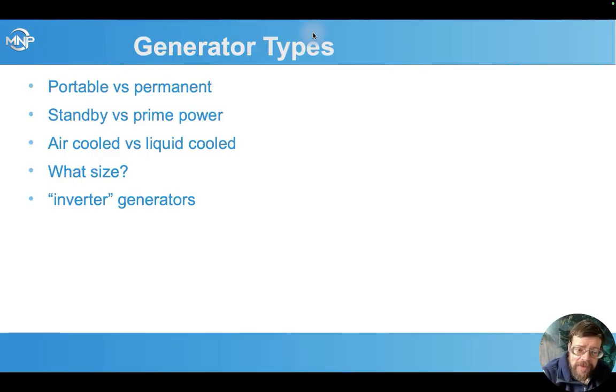What size generator? The MidNite inverter can pull 10 kilowatts for battery charging, and that's in addition to the pass-through for loads. So usually we recommend a 12 to 15 kilowatt generator minimum, but it can depend on your situation. You can reduce the battery charging rate to allow using a smaller, say a 6 to 7 kilowatt portable generator. It's just going to charge the batteries at a lot slower rate, and you really want to watch out for overloading those smaller generators and really causing even shorter lifespan on them.